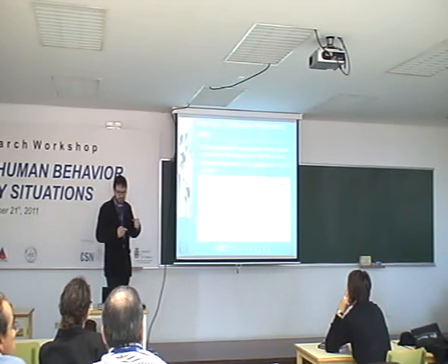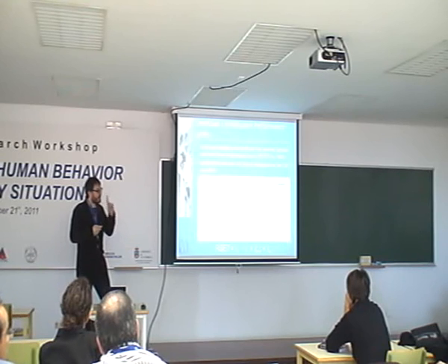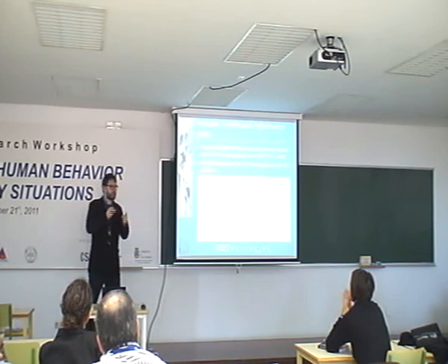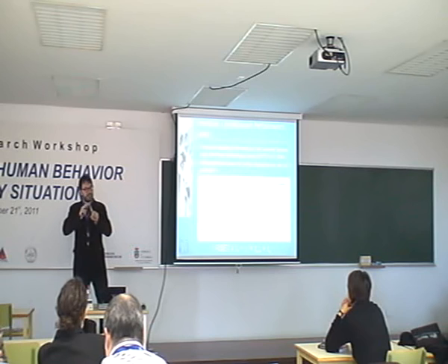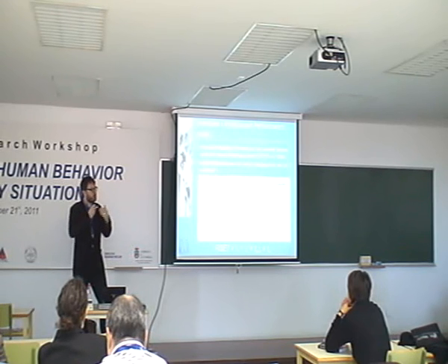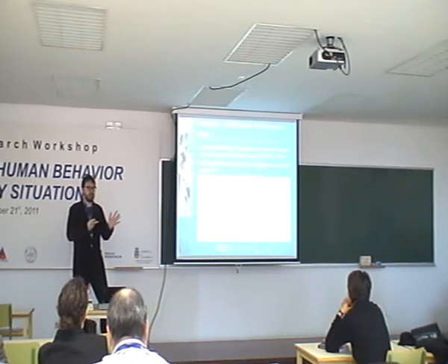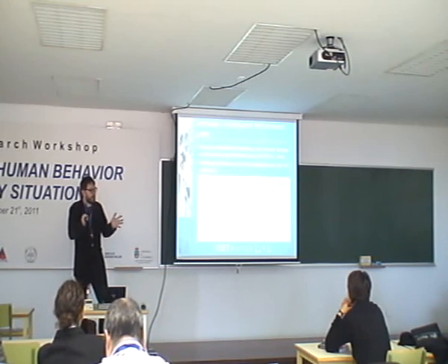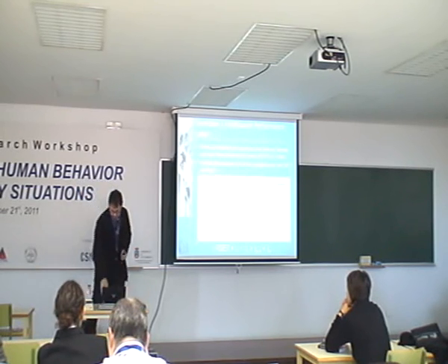Now, in this paper, what we're doing is coming up with a crude way of estimating or accounting for this notification time, given the procedure that's in place. I'm not attempting to predict staff actions on an individual level, but given that a certain procedure is in place, and the method of sensing an incident, and the method that is intended when the alarm is distributed, you can then account for the number of staff decisions that are required as a bare minimum. So you can at least get a broad estimate of the expected delay time before the general alarm is even enacted, and then the population begins to evacuate.